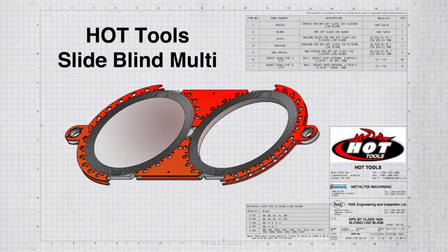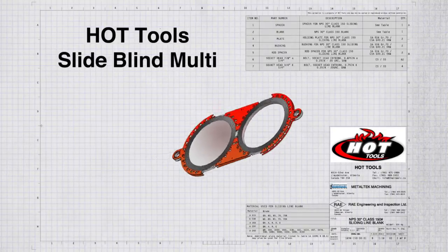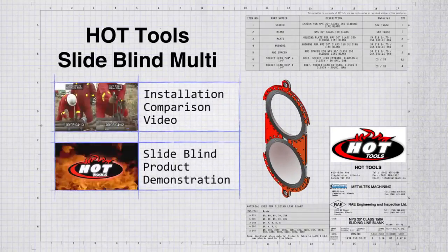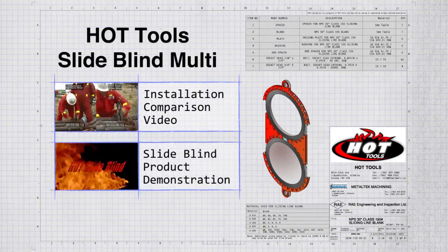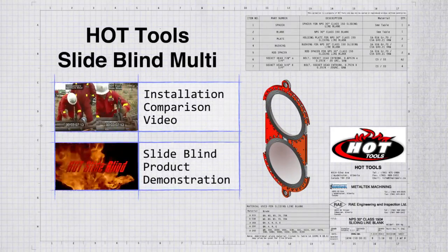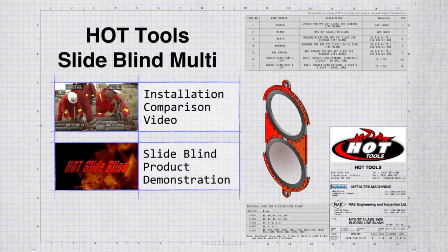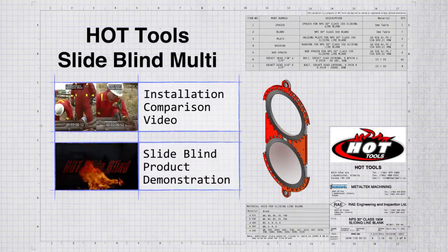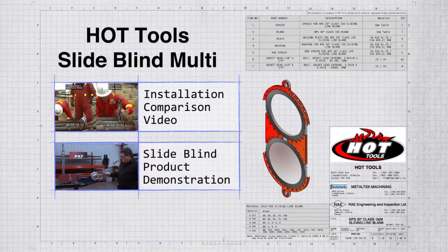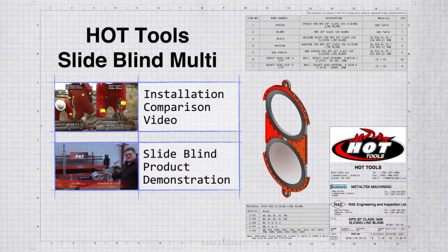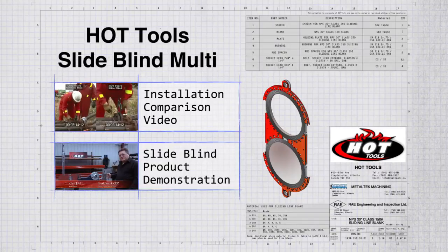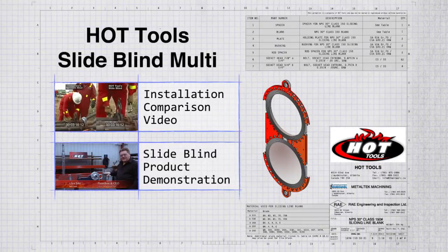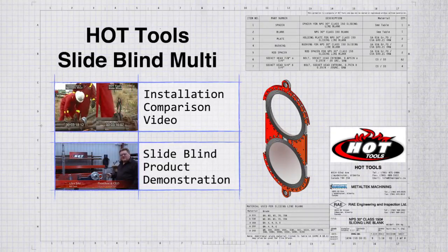Based on the ASME B16.48 certified design of the original Hot Tools SlideBlind, which replaces traditional line blind variants such as the spectacle and slip blind and reduces blanking operation time by up to 50%, the SlideBlind Multi is a multi-piece pipe blanking tool particularly convenient in larger format applications.